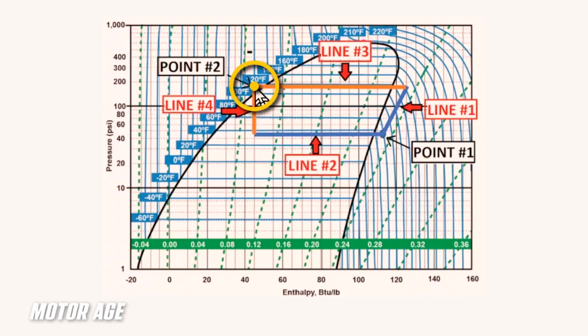This next point here represents temperature just before the metering device. So this is about 120 degrees Fahrenheit shown here, and high side pressure as well, just below 200 psi. So this line will be carried out straight to the right to intersect this line here, and it will drop straight down as well. The horizontal line represents the energy exchange at a fixed temperature across the bell curve as we cross the condenser and shed heat.